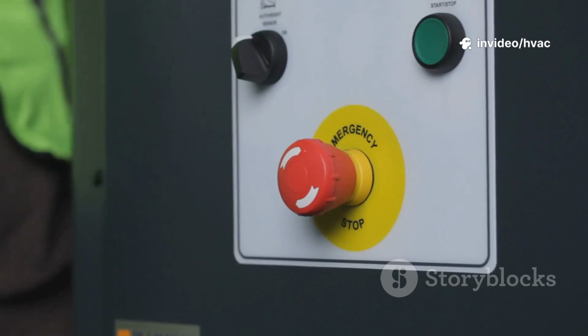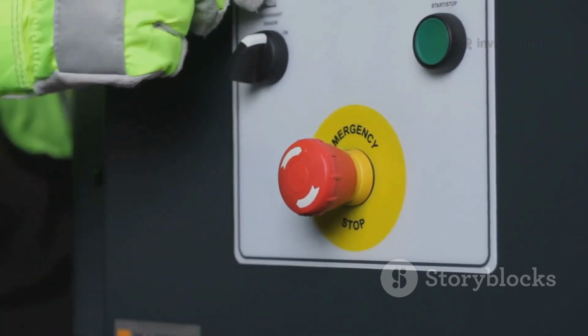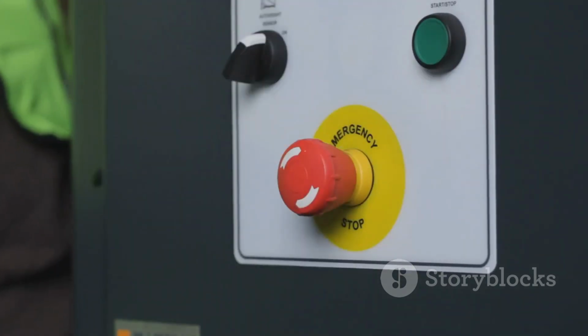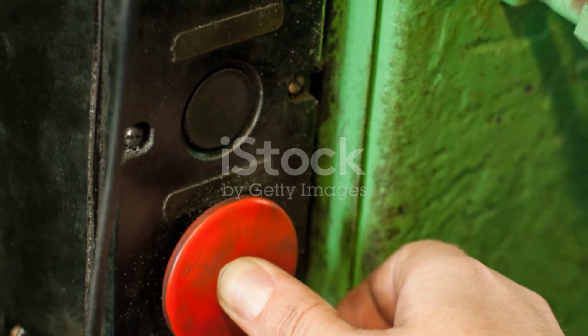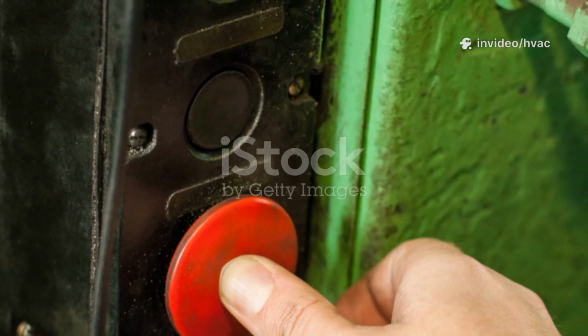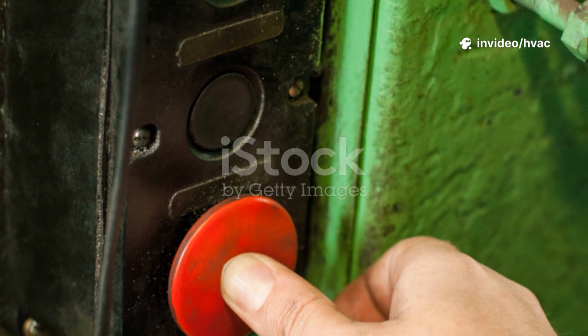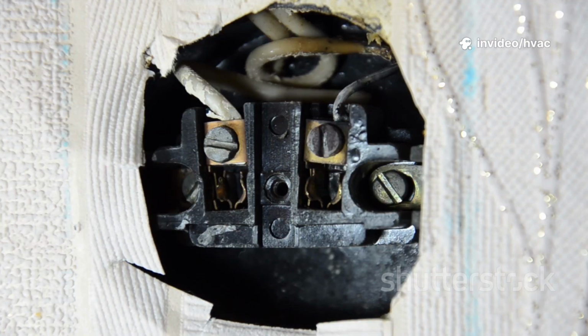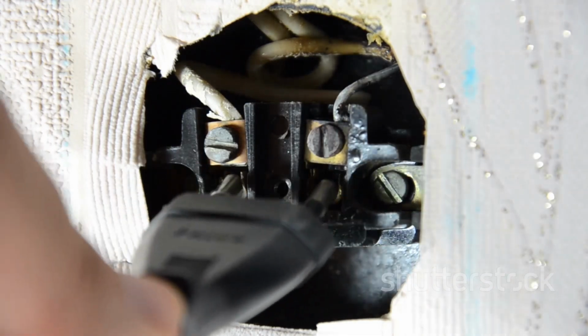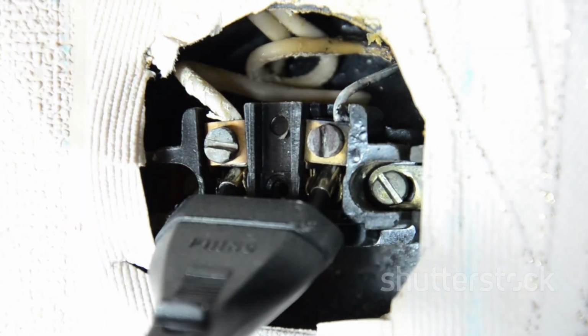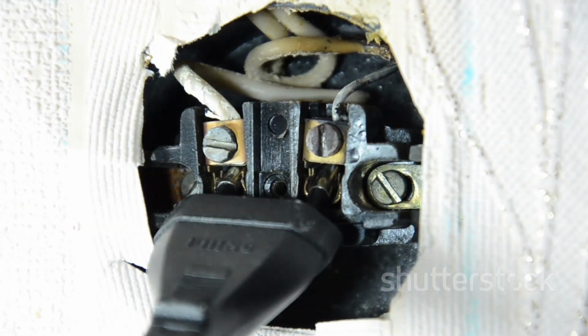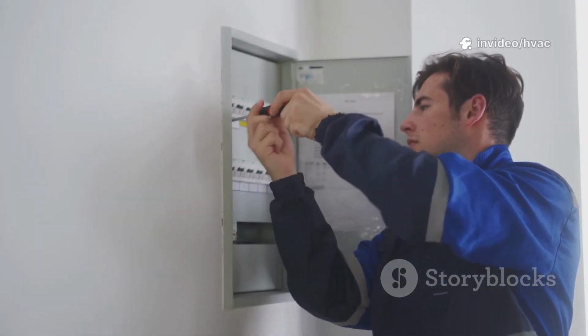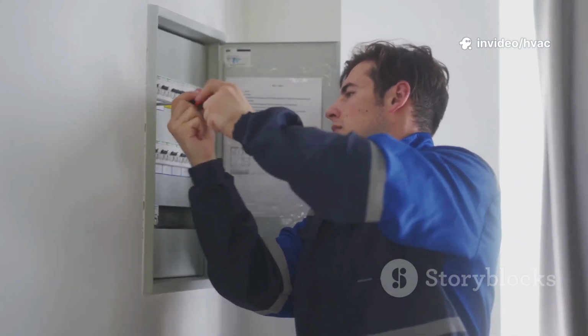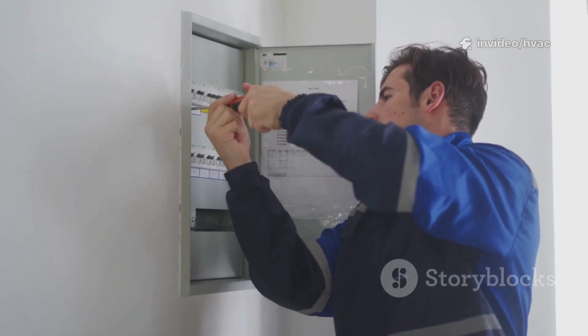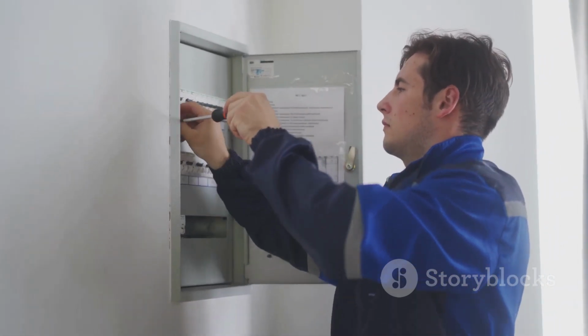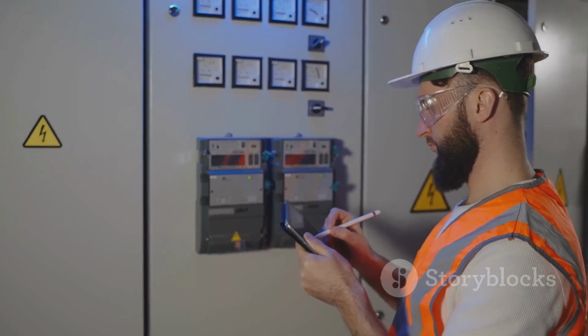All these contacts, the NO for pump run, NC for flow, and NC for low temp, are wired in series to form a permissive circuit. If any NC opens or if the NO stays open, the chiller won't start or will shut down. This same logic applies to air handling units with VFDs. The fire interlock NC, overload NC, and VFD run feedback NO are all part of the permissive circuit. If any NC opens, like the fire interlock or overload, the AHU won't run. If the VFD run feedback NO doesn't close, the system knows the fan isn't running and will stop. This ensures any failure results in a safe shutdown.